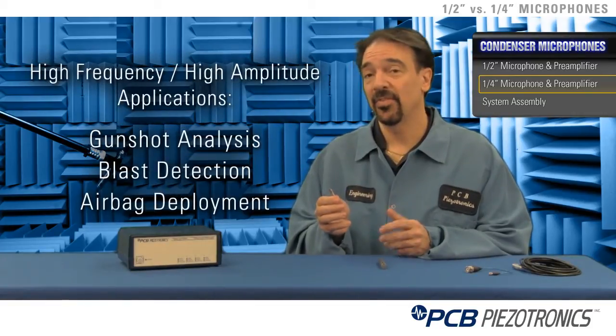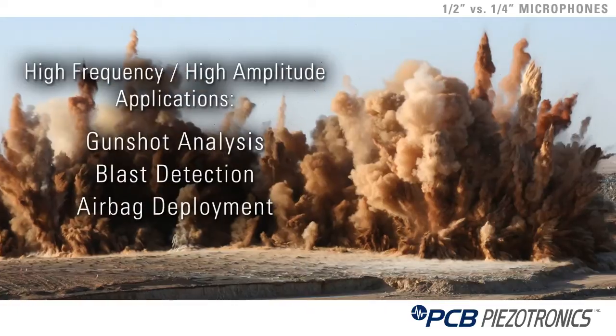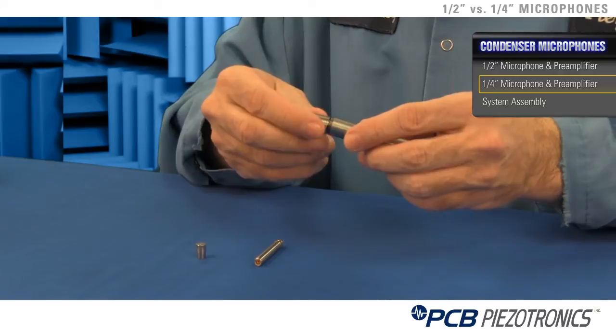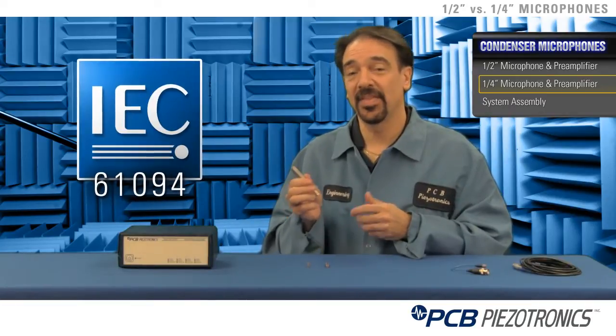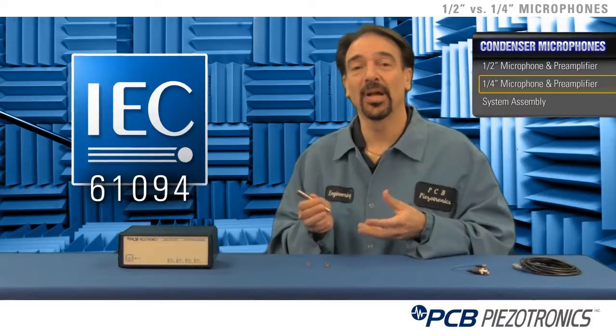Quarter inch microphones are most commonly used for very high amplitude, high frequency applications such as gunshot or any other loud noise. The microphone and preamplifier gets put together with a standard thread that's dictated by an IEC 61094 standard, which ensures interchangeability between all manufacturers who comply with the standard.